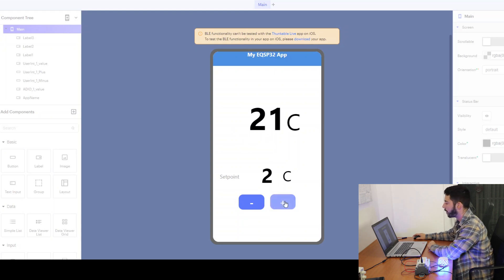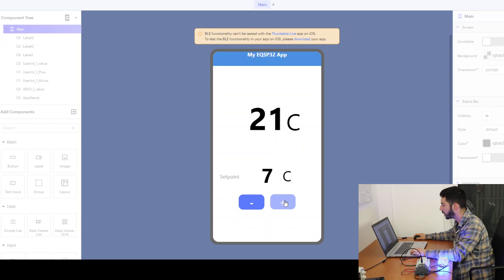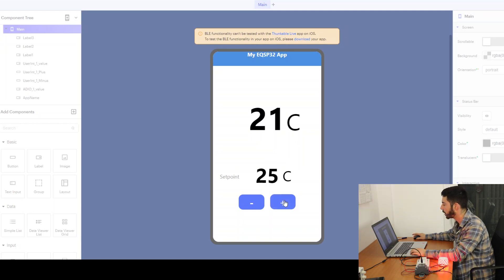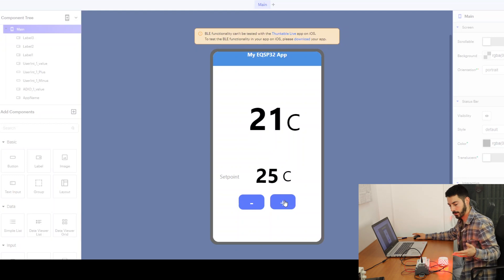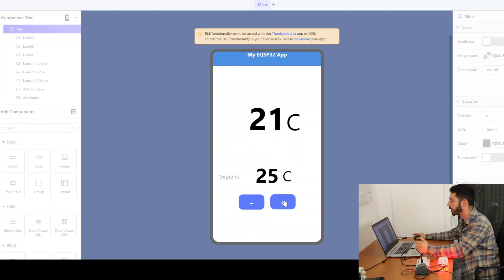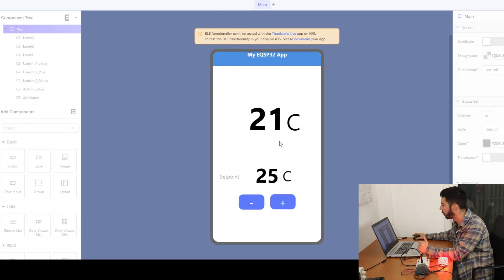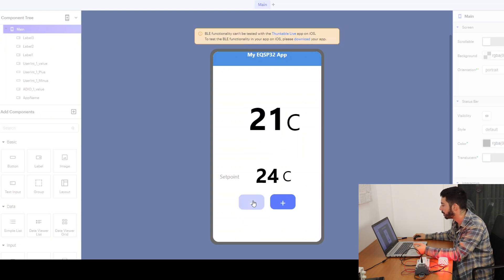If we now set this set point to let's say 23, we expect to see the LEDs turning red and the relay to turn on. This would result in the heater turning on.